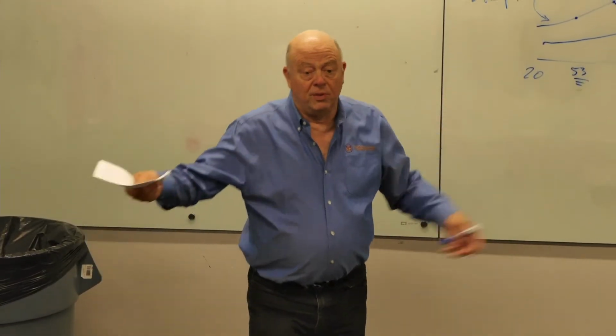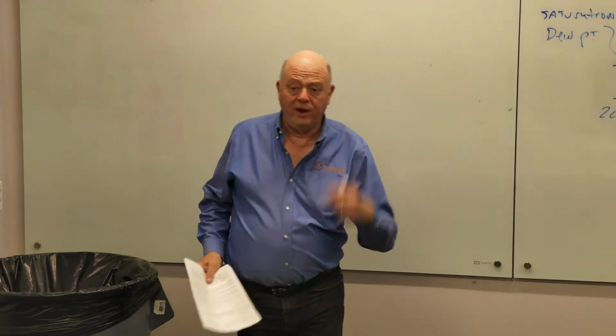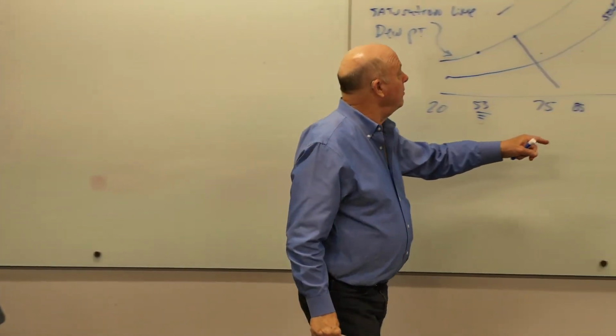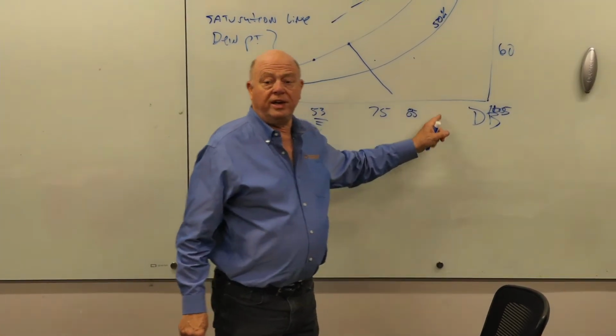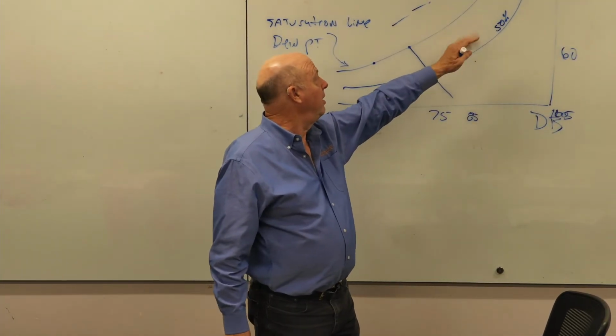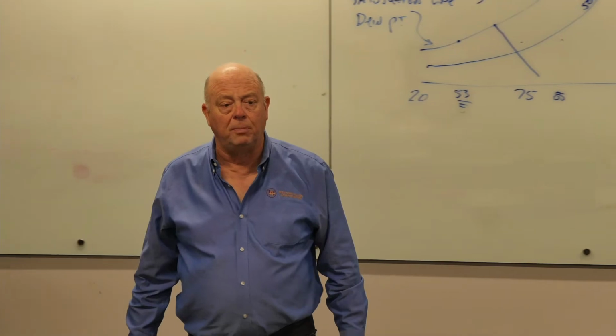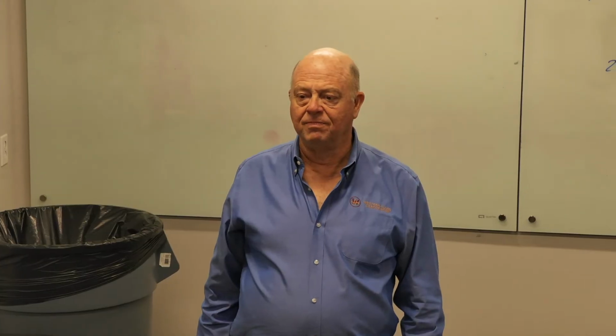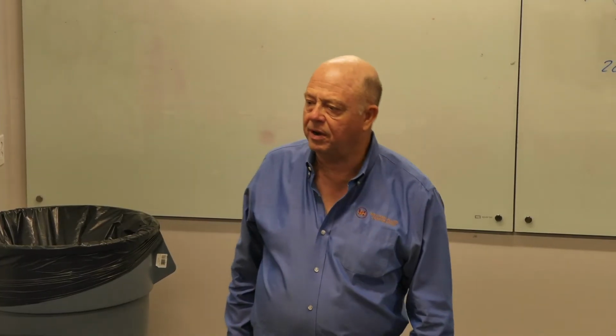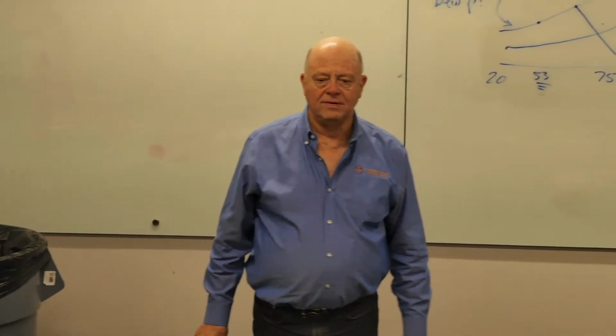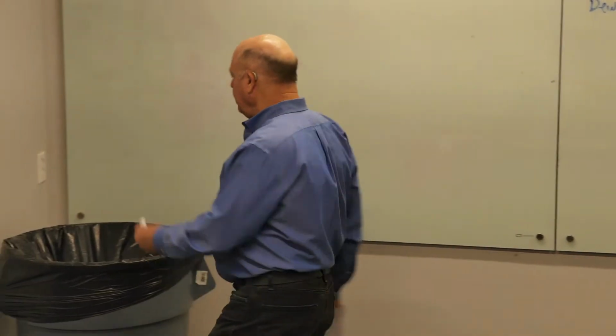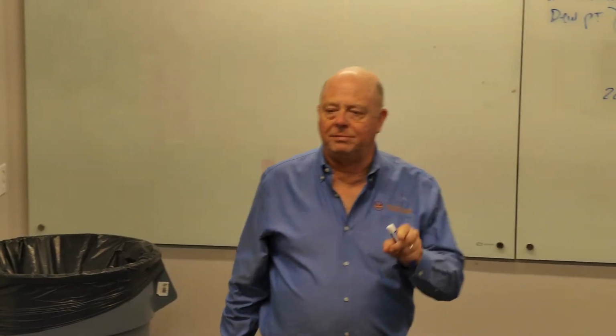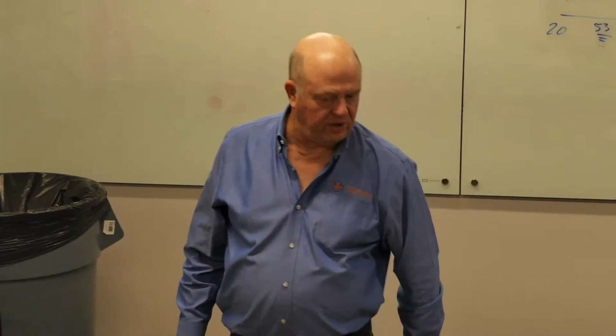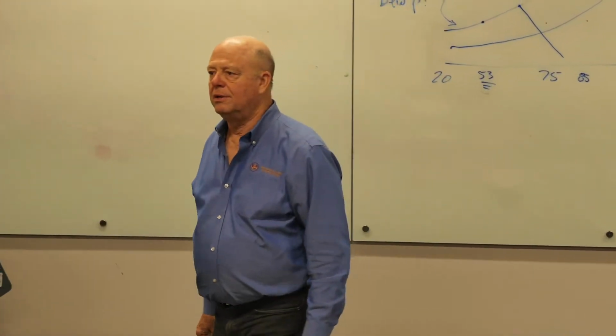And it's the same principle that we've been talking about with all this other stuff, right? It's the dew point versus what's the temperature. And the dew point in that attic, let's just pick a number. Let's say that your attic temperature is 90 degrees and about 80% relative humidity. What's the dew point? I haven't looked this one up, so I don't have my crib notes. One of you guys are going to have to tell me. 90 and 80% relative humidity. Like 79, 78. Okay. I will guarantee you there will be times when the condensate drain line will be colder than 78 or 79 degrees. Like always.